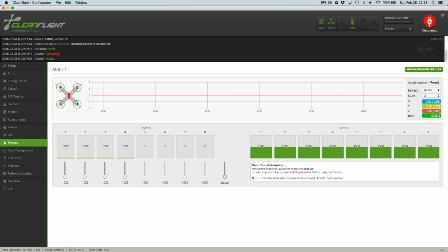And when I go down to 1032, they start to stutter. That's the point that you're looking for. So go back to 1034 and add 10 at least. You don't want to go too high, but add about 10. So that's 1044. Look at your motors and listen to your motors.